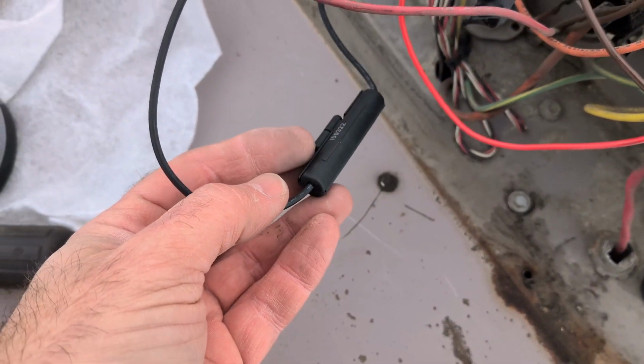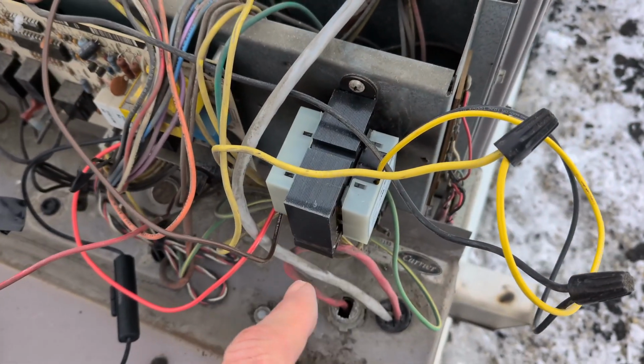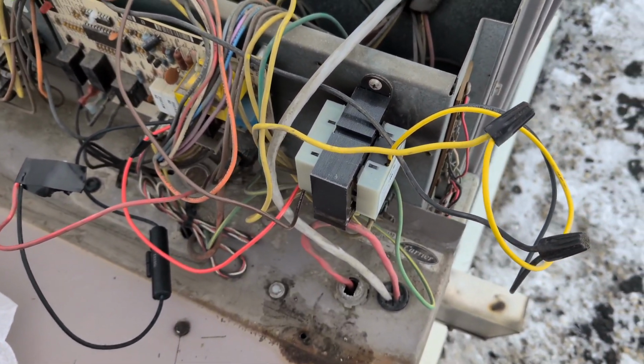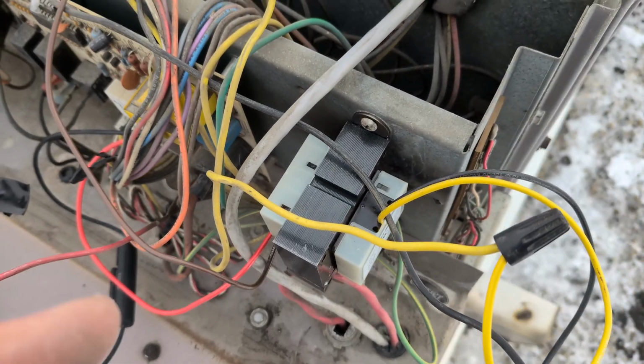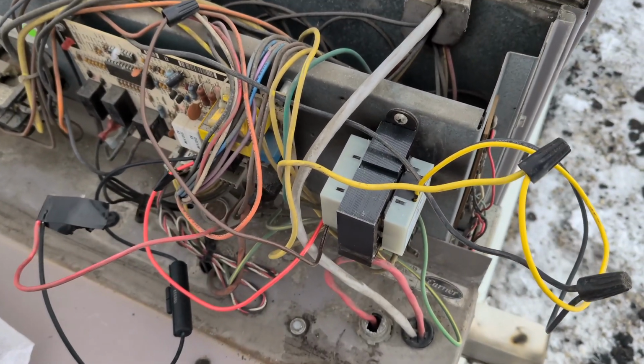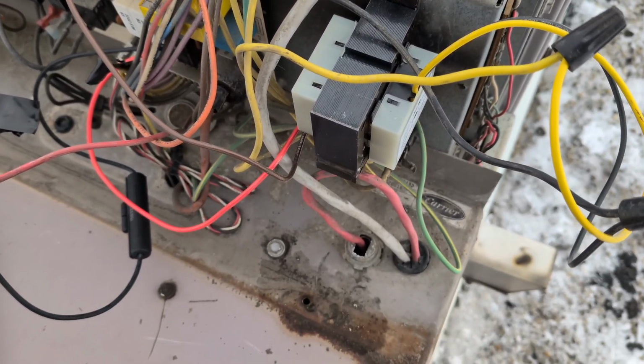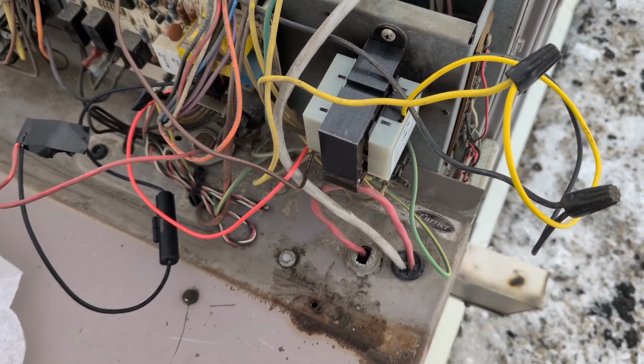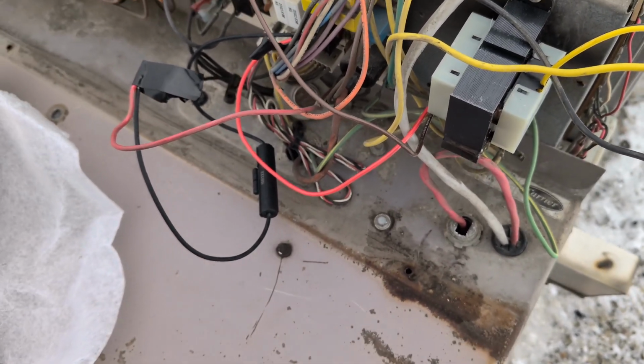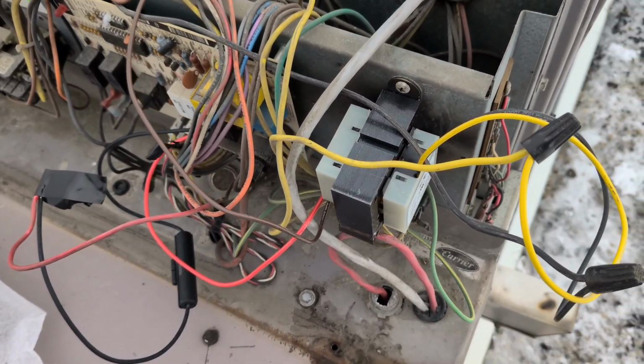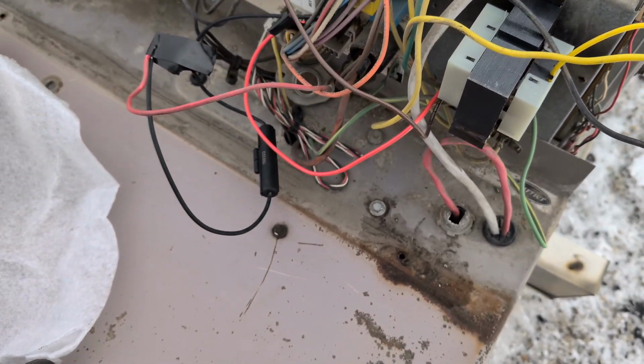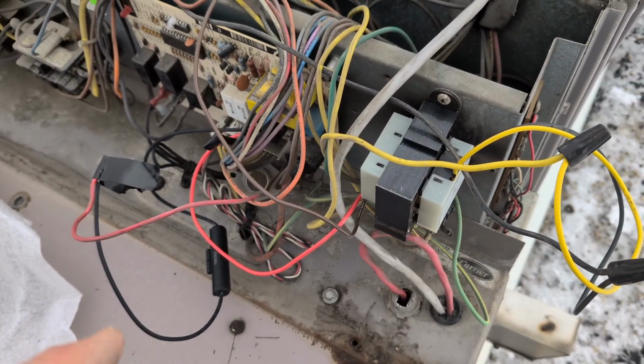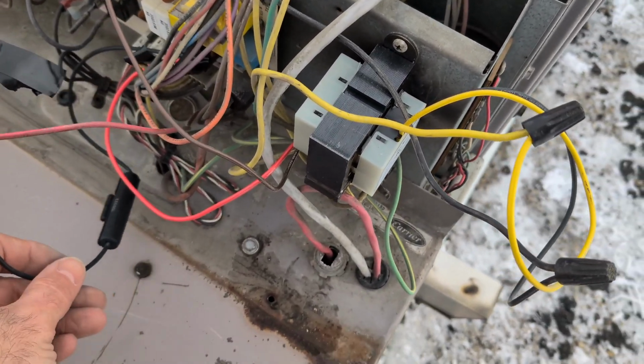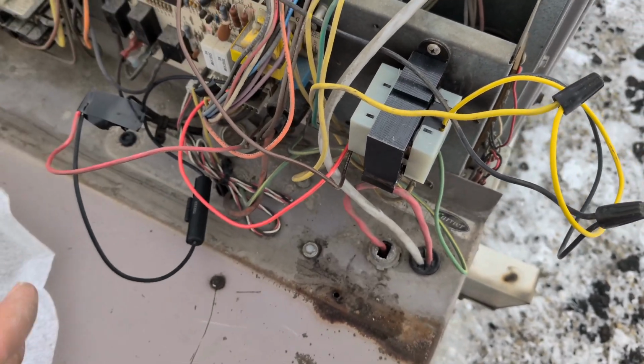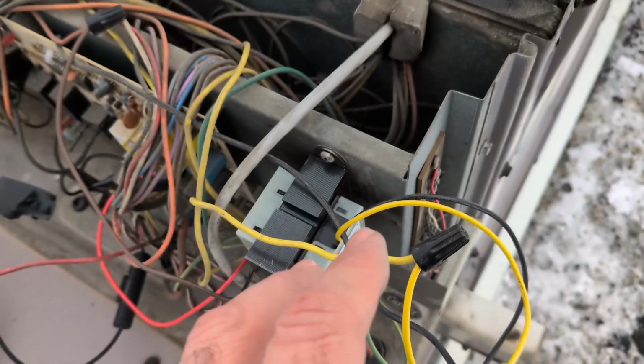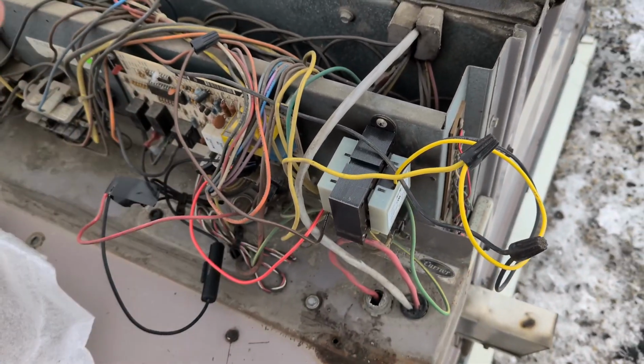Now, how do you size this fuse? Well, the transformer is a 40 VA. It's 24 volts on the control side, so we go 40 divided by 24. That gives us 1.66 amps. So you're probably not going to find a glass fuse that's 1.66 amps. So you're going to have to decide whether you use a 1.5 or a 2. They only had 1.5s at the supplier, so I've got a 1.5 in here for now, which will give me protection as I'm testing this transformer and protection going forward.